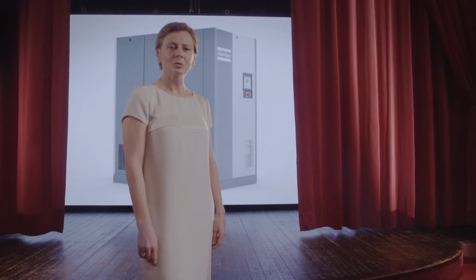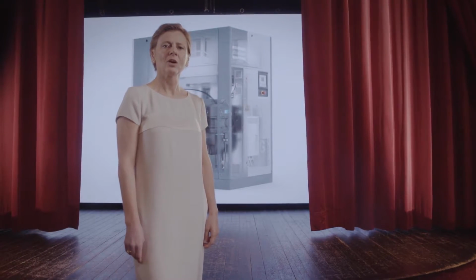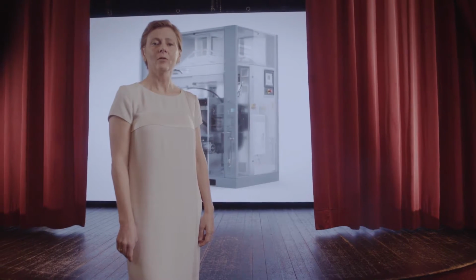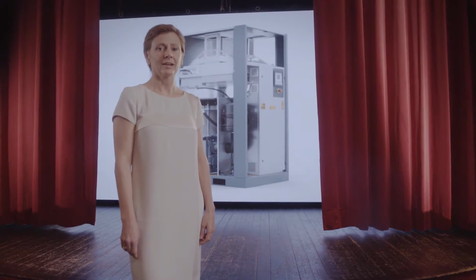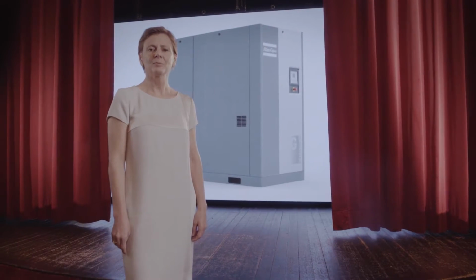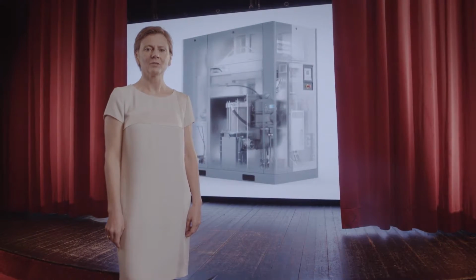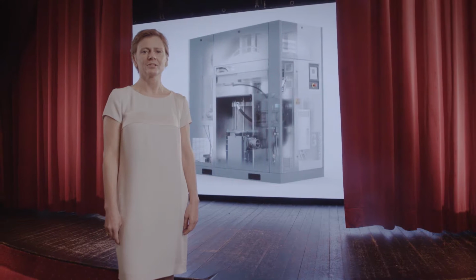This new GA VSD Plus range builds on the successes of the small VSD Plus, but also on the proven performance of the previous VSD range. Take the cooling of our oil. For that we rely on the tried and tested technology of the 37 to 90 VSD range. We use the classic aluminium air-oil cooler and air-air cooler design. As is the case in the current VSD range, the water separation has been integrated in the design. Coolers were generously sized, allowing the machines to work in the harshest conditions.